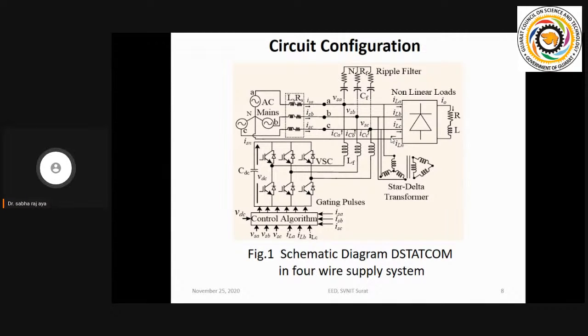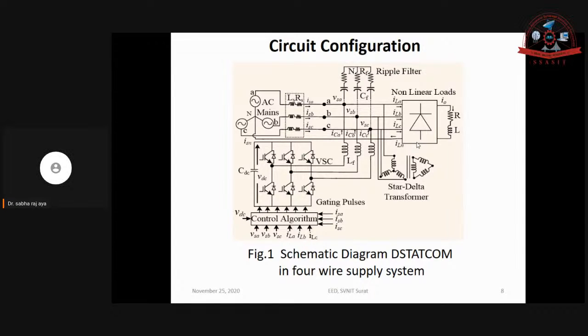After compensation, we have a different value. Means we have a star connection, and at the midpoint of that star connection you are going to connect the neutral wire. This system is going to compensate the neutral current, so our transformer neutral current and load neutral current are equal and opposite in phase. If both are equal and opposite in phase, at that time we are going to observe zero neutral current at the supply side. Okay, means the transformer is going to provide an equal and opposite compensating neutral current.